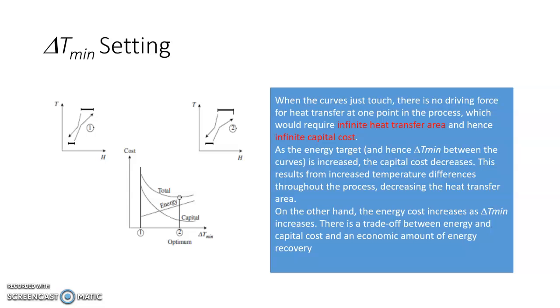Delta T minimum is a key factor in designing heat exchanger network or in identifying the targets for energy. As I have shown you here in this diagram, in diagram one, delta T minimum is less and delta T minimum in diagram two is more. Now the impact of delta T minimum is as you decrease delta T minimum, naturally the process to process energy exchange would be more and your energy requirement would go down as you can see from the width of these columns which are shown for utility. So as you increase delta T minimum, utility also increases. However, increasing delta T minimum will impact the area of exchanger.